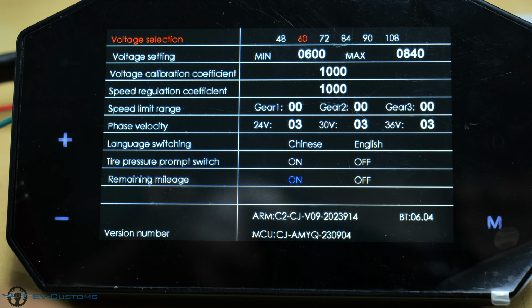Pressing mode continuously again, the second line shows voltage limits: the minimum and maximum voltage of our system. If we've chosen a 60 volt system, the minimum voltage must be about 48 volts. By factory settings, the screen saves minimum at 60 volts and maximum at 84 volts. We must change it from 480 to 672, meaning 67.2 volts maximum.